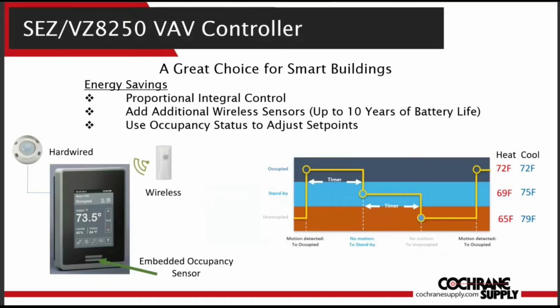8250 room controllers have 3 set points: occupied, standby, and unoccupied. When the controllers sense motion, they control to the occupied set points. If no motion is detected for a user-defined period of time, the room controllers will change from occupied set points to standby set points and begin another timer. If no motion is detected for that user-defined period of time, the room controllers will change from standby set points to unoccupied set points. If at any time motion is detected, the controller will revert to controlling to occupied set points once again. There's no need to condition a space to occupied set points when there's no occupancy.